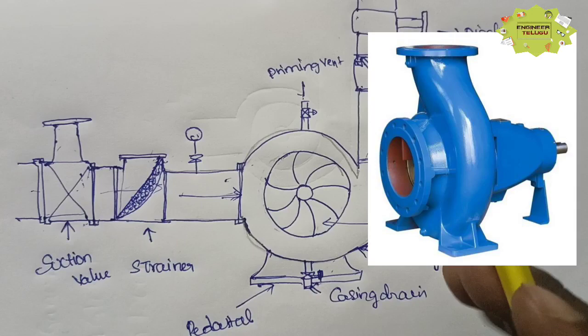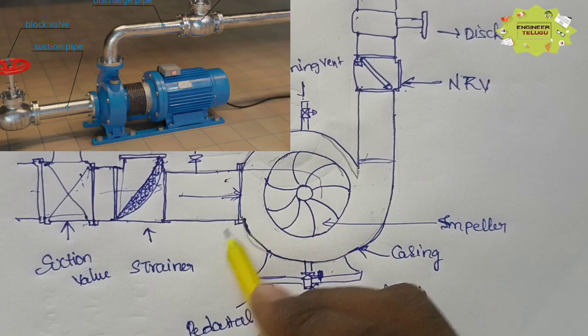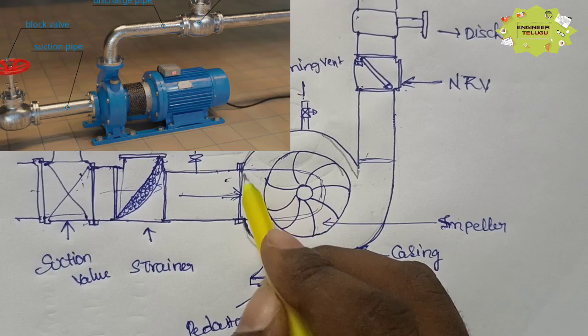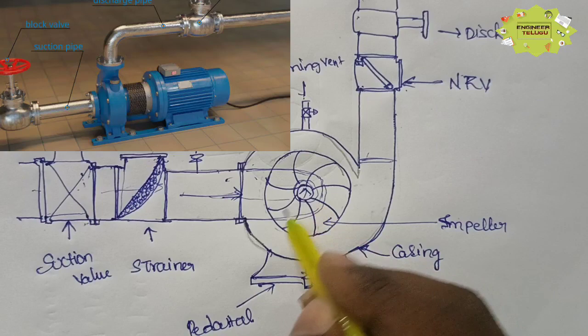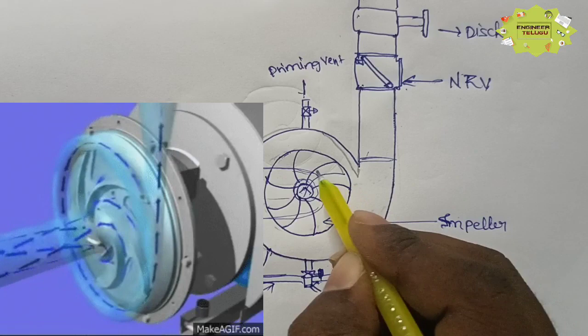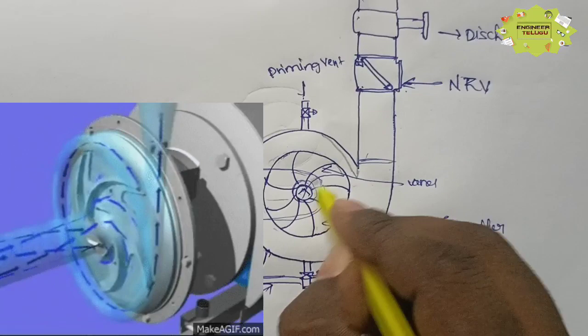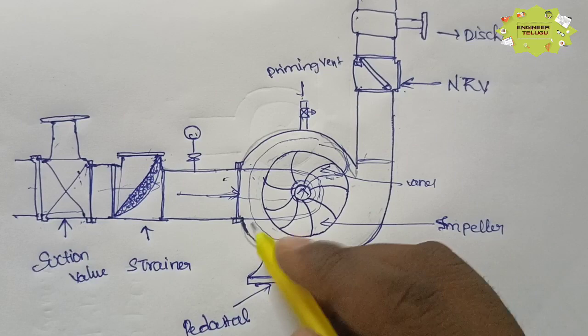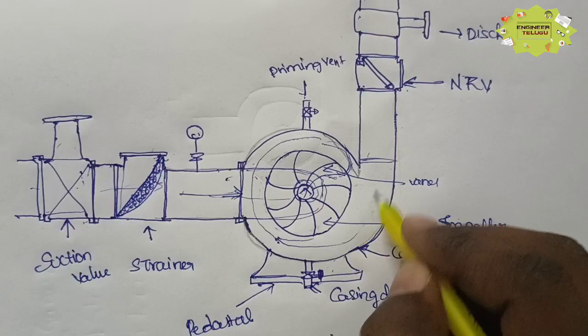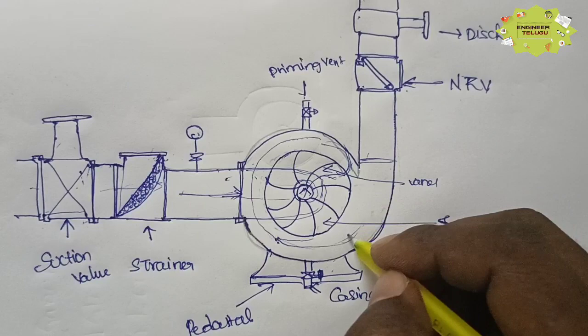The casing is a big volute shape and it is closed. The suction pipe connects at the inlet flange. The flow enters from the center and the impeller rotates from the center, converting velocity energy into pressure energy. The casing is the first stage where flow is directed. This is the impeller.